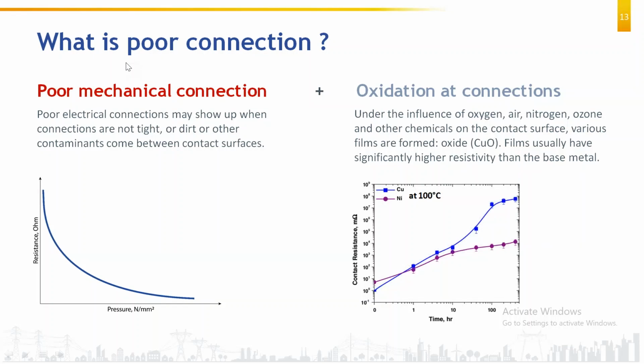When the contacts are making and breaking, at that time there is a connection and there is a break in the connection. In both these cases the issues can be different. The issues of loose connection can be different. For example, in a loose connection where you are using cable lugs or bus bars and terminating them on a terminal block, the issue can be that your connections are not tight or you have oxidation at the connections, meaning your connections have caught rust. These can be the causes.